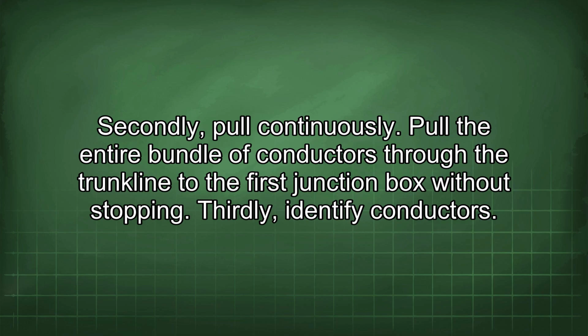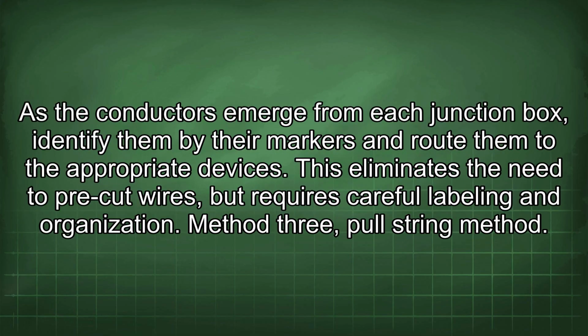Secondly, pull continuously. Pull the entire bundle of conductors through the trunk line to the first junction box without stopping. Thirdly, identify conductors. As the conductors emerge from each junction box, identify them by their markers and route them to the appropriate devices. This eliminates the need to pre-cut wires, but requires careful labeling and organization.